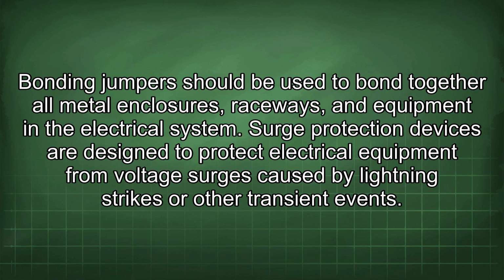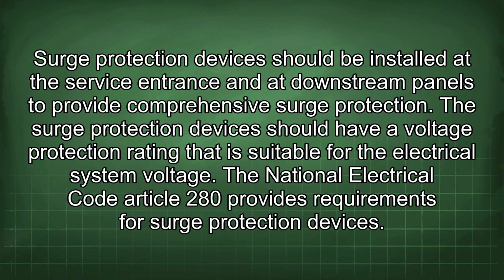Surge protection devices are designed to protect electrical equipment from voltage surges caused by lightning strikes or other transient events. Surge protection devices should be installed at the service entrance and at downstream panels to provide comprehensive surge protection. The surge protection devices should have a voltage protection rating that is suitable for the electrical system voltage. The National Electrical Code Article 280 provides requirements for surge protection devices.